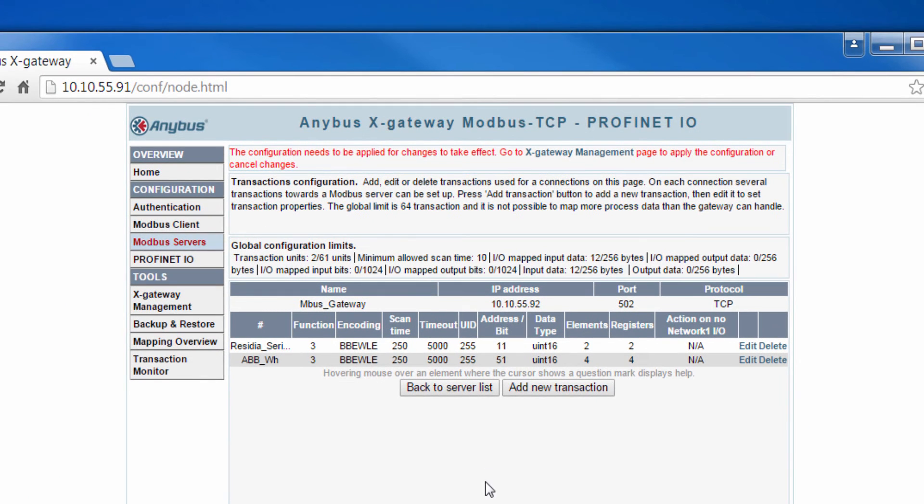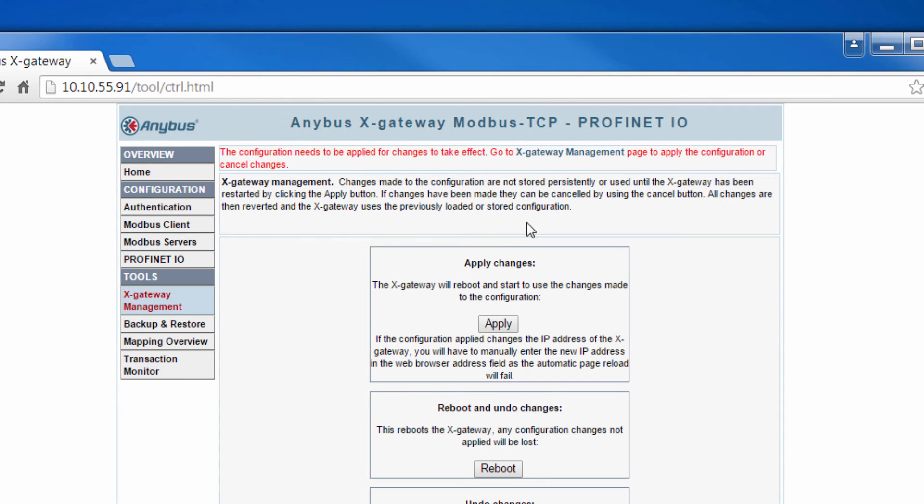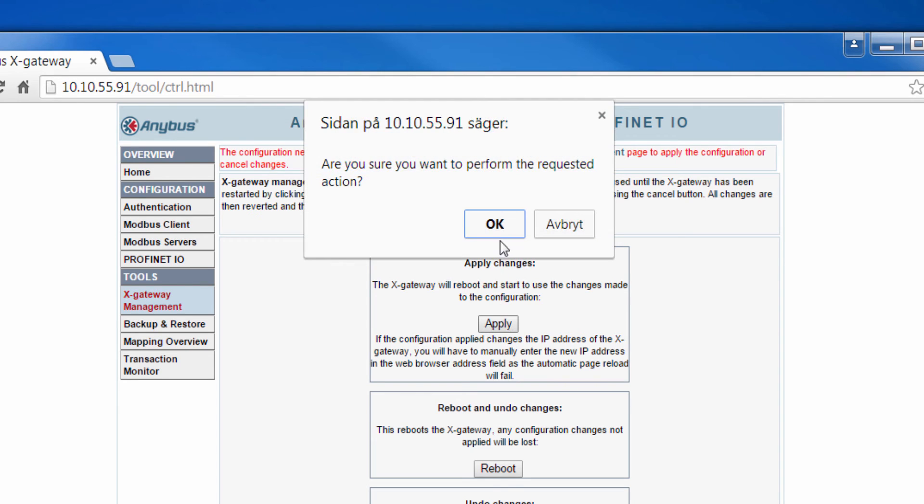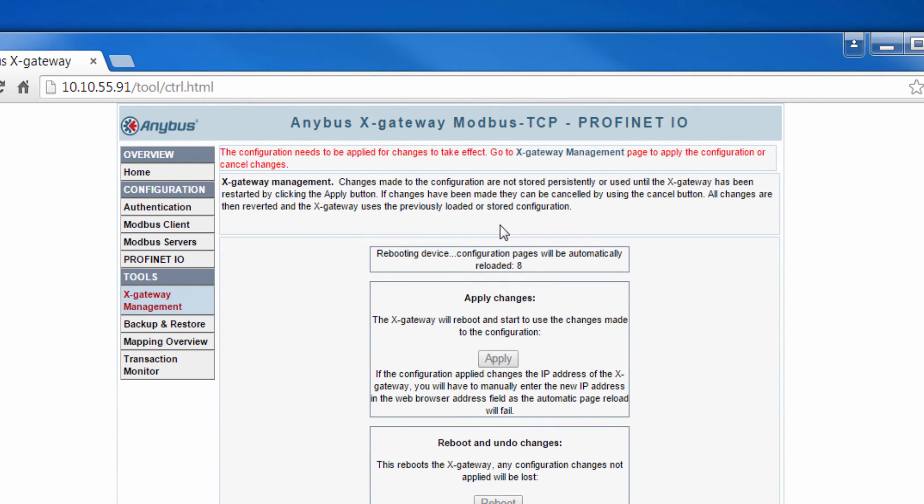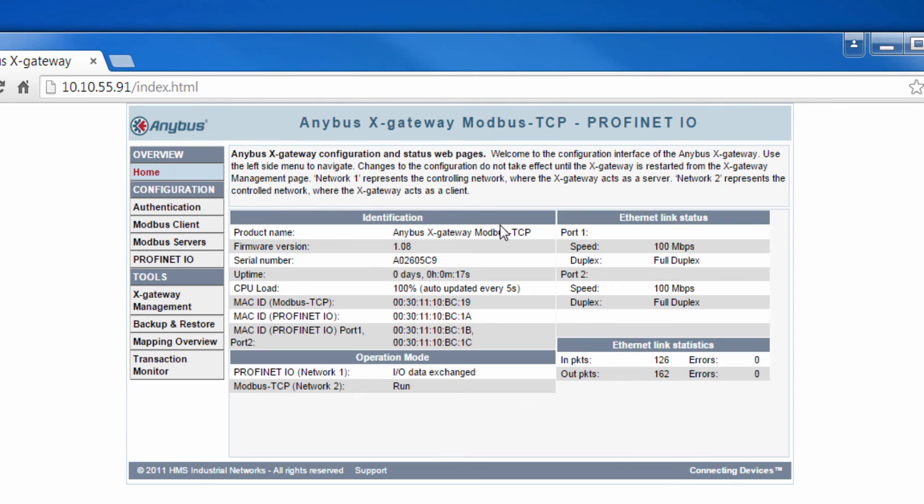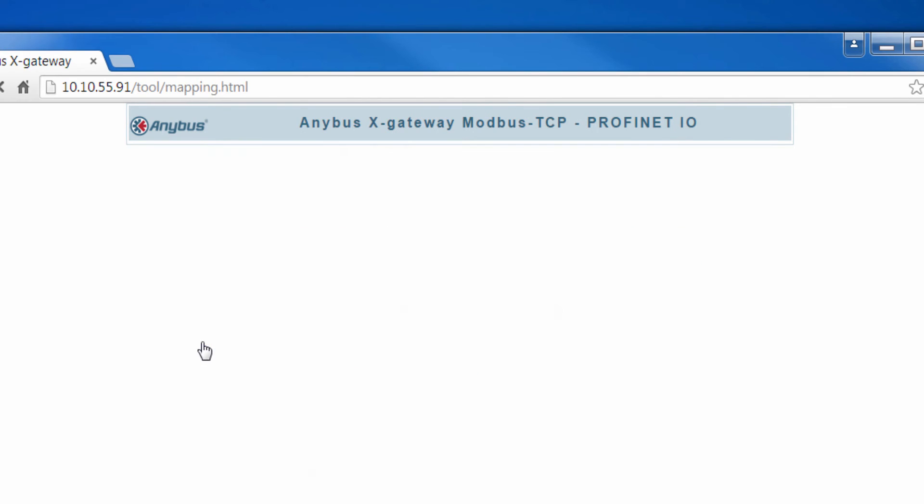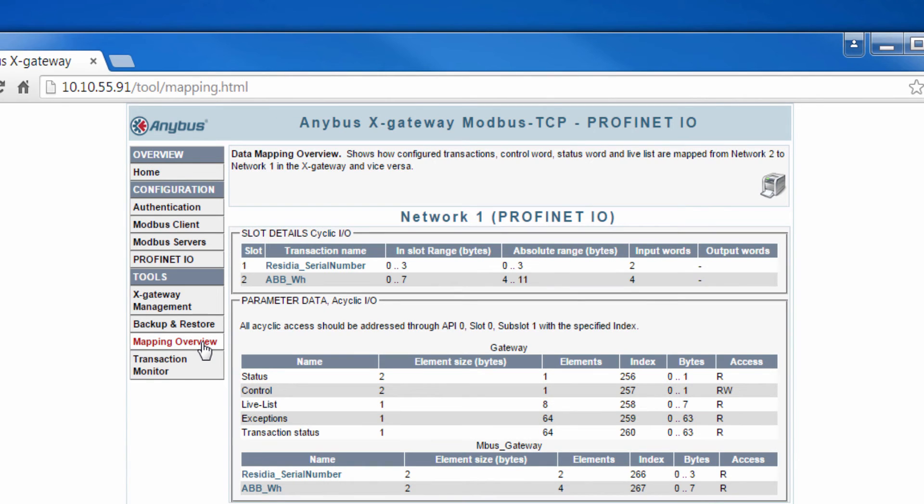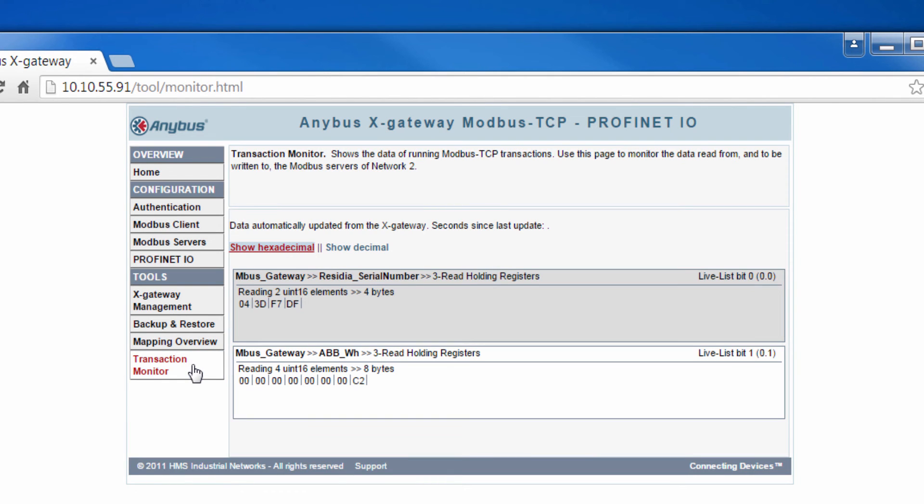I now go on to x-gateway management to apply my changes. When this is done, I go to mapping overview where I can see what it will look like from the PLC side, how I need to map things as a PLC programmer. In the transaction monitor, I can see whether the Modbus queries are working, that is if we are receiving any data from the MBUS side. This seems to be working, so now we can switch to the final part, getting the values from the MBUS devices into TIA Portal.